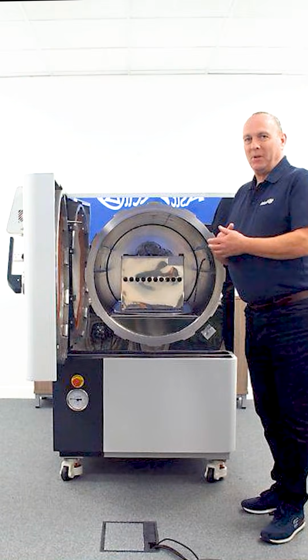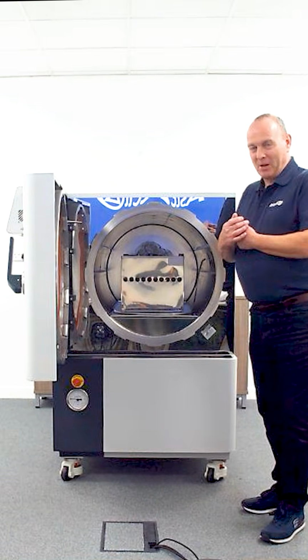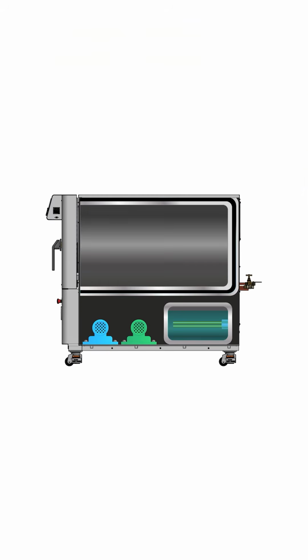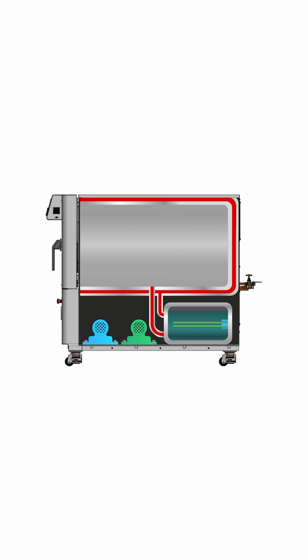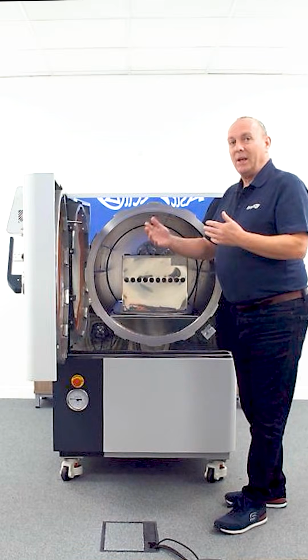We do have the option of a vacuum machine with a steam generator and a jacket. This would make the process of sterilisation of a plastic discard load quicker, because it would evacuate the air out of the load quicker with a pre-vacuum, negative and positive pulsing. It would then sterilise for your nominal period at 121, 15 minutes or above. And then it would pull a big vacuum at the end to suck all the air and the steam out of the chamber and make the whole process faster.